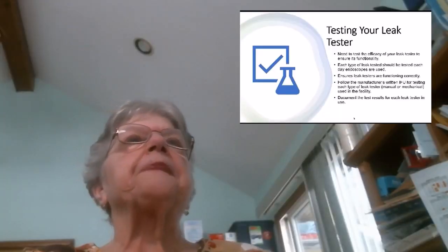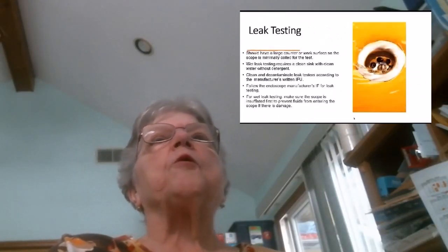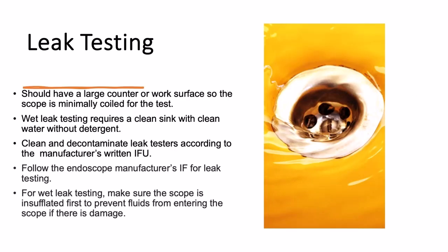You should have a large counter or work surface so that you can leak test your scope, and it's minimally coiled. Remember, the more tightly you coil it, the more possibility of damage to the fiber optics. Wet leak testing requires a clean sink with clean water without detergent. If you have detergent, you're going to get bubbles, and it's going to interfere with your test results. Clean and decontaminate your leak testers according to the instructions from the manufacturer. Follow the manufacturer's instructions for leak testing.